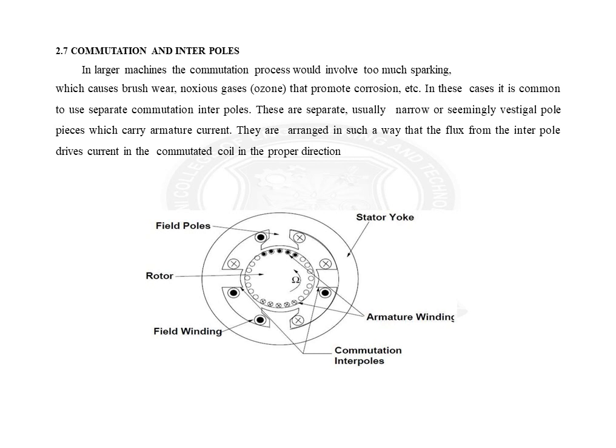These are separate, usually narrow pole pieces, which carry armature current. They are arranged in such a way that the flux from the interpoles drives current in the commutating coil in the proper direction.